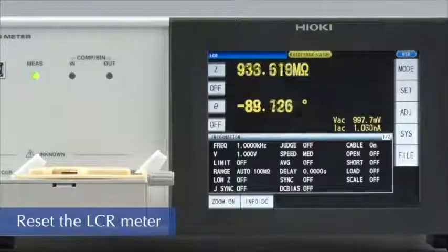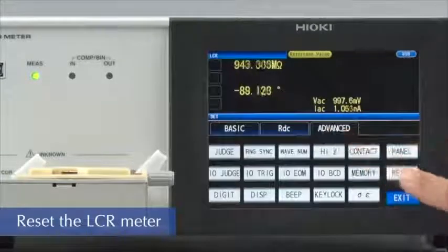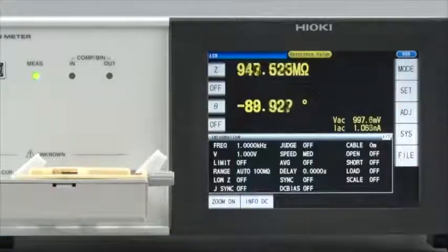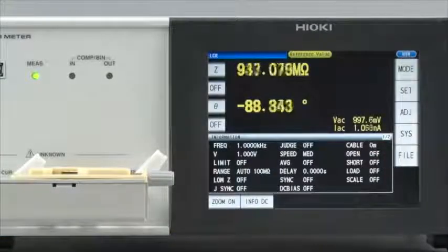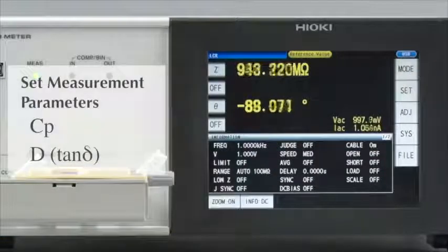First, return the LCR meter to default condition by touching Reset on the screen. All of the settings are now in their default state. Now, let's set the measurement parameters.